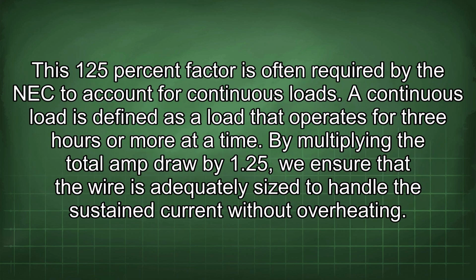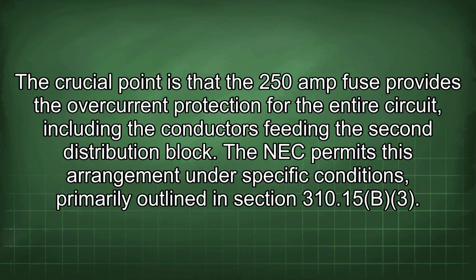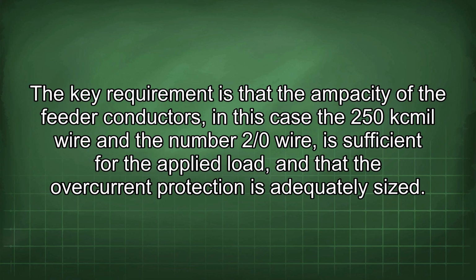This 125% factor is often required by the NEC to account for continuous loads. A continuous load is defined as a load that operates for 3 hours or more at a time. By multiplying the total amp draw by 1.25, we ensure that the wire is adequately sized to handle the sustained current without overheating. The crucial point is that the 250 amp fuse provides the overcurrent protection for the entire circuit, including the conductors feeding the second distribution block. The NEC permits this arrangement under specific conditions primarily outlined in Section 310.15(B)(3).